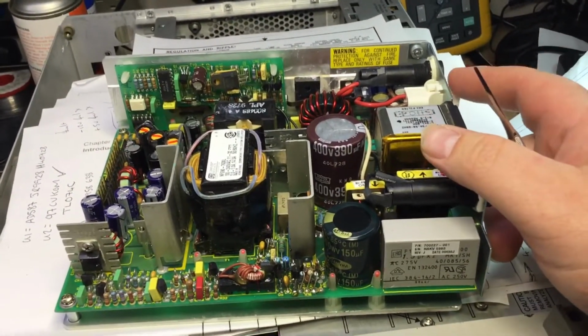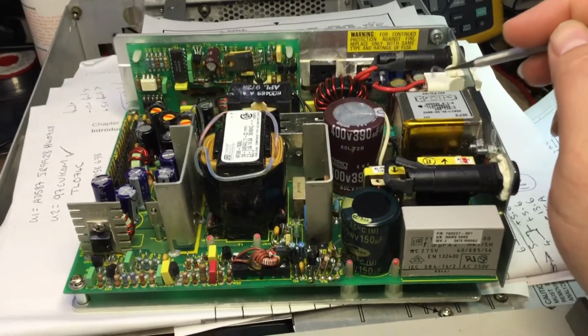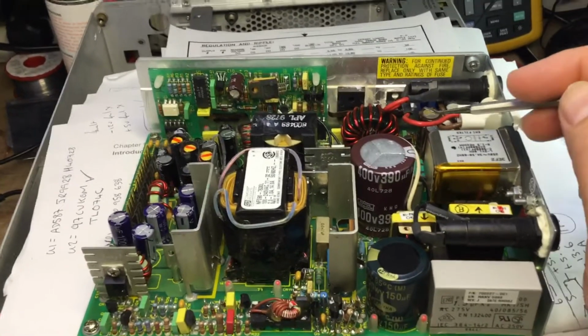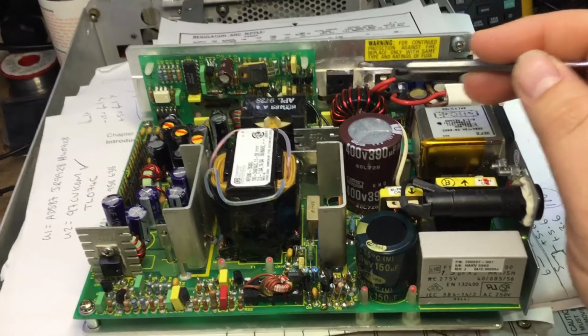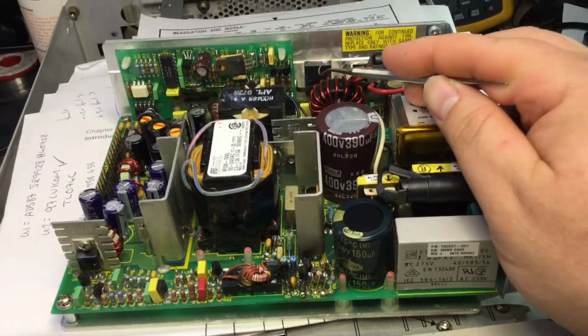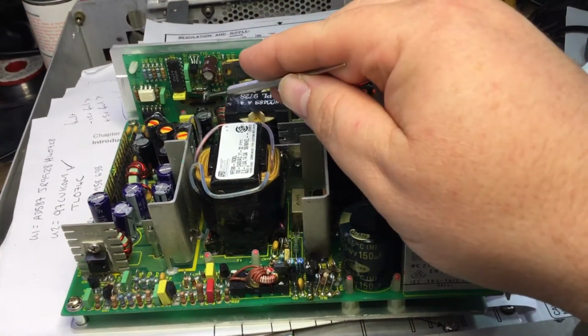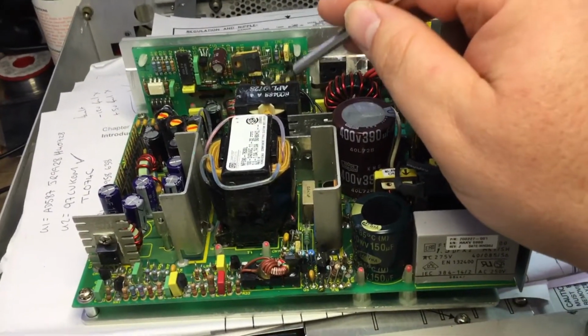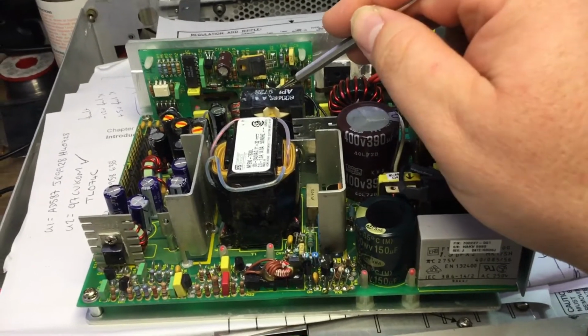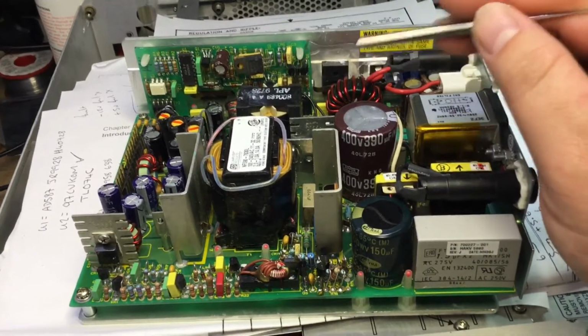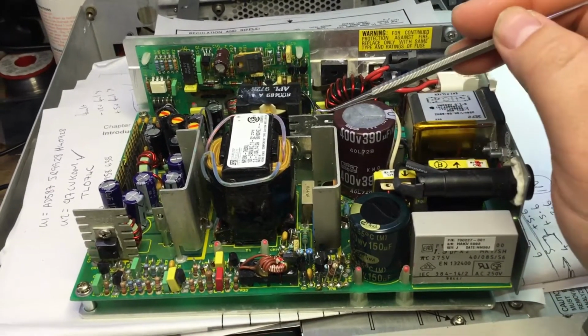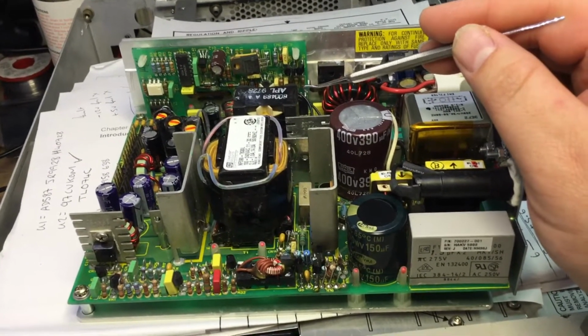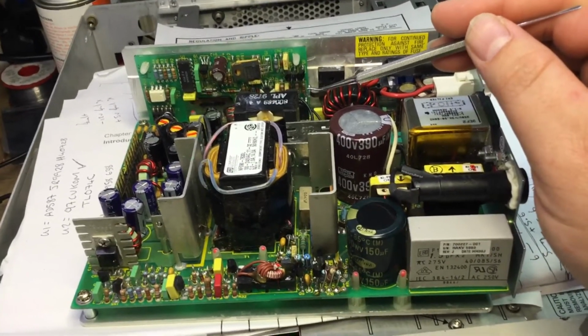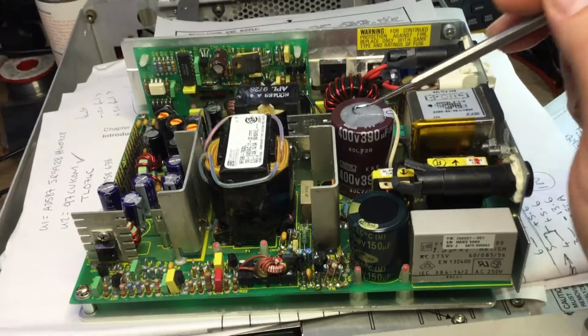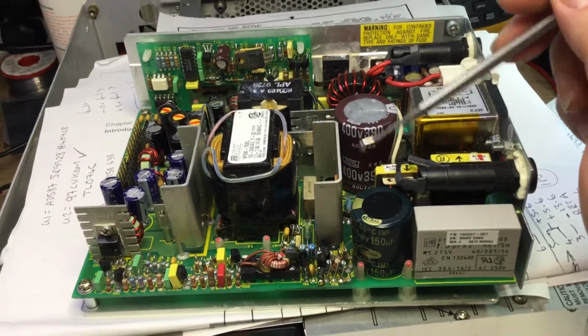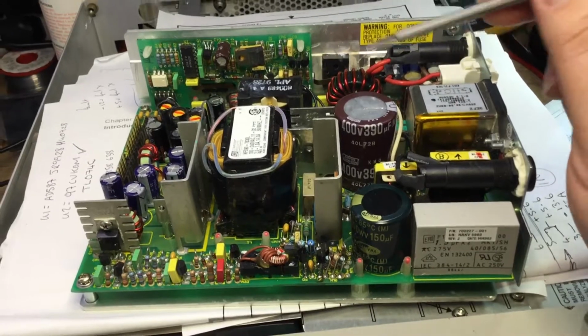If we take the battery supply here, that enters the supply and is switched by two big transistors here and here, hidden behind this board. This transformer, located where this was pointing to, is switched on the primary side, and this is a step-up transformer, which then goes through a bridge rectifier and supplies voltage to these two reservoir caps, charging them up to around 350-360 volts DC.